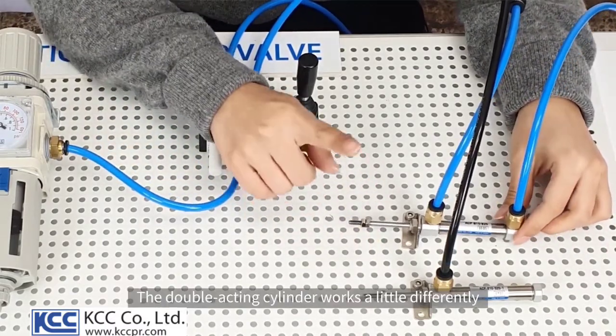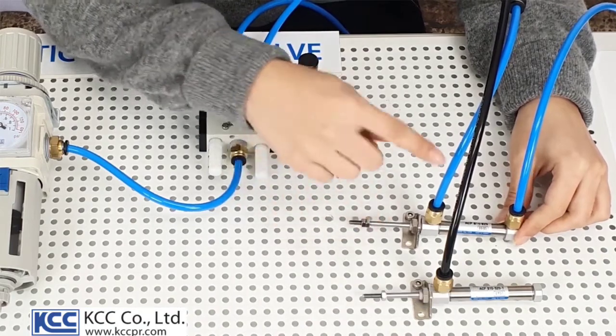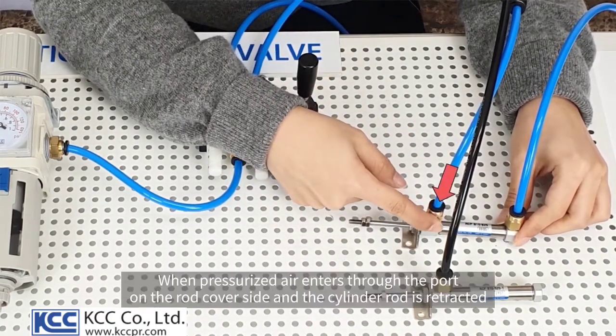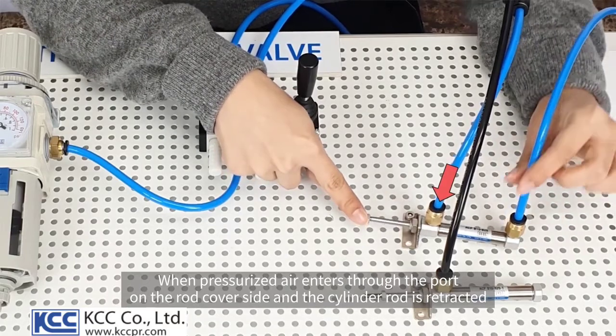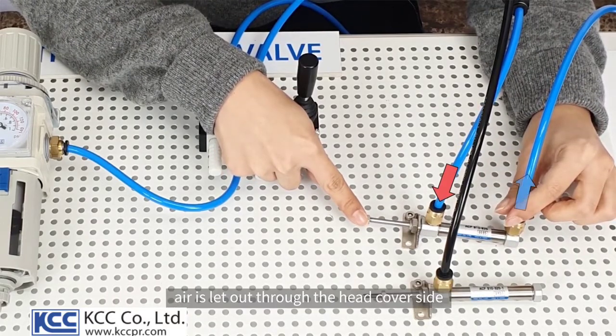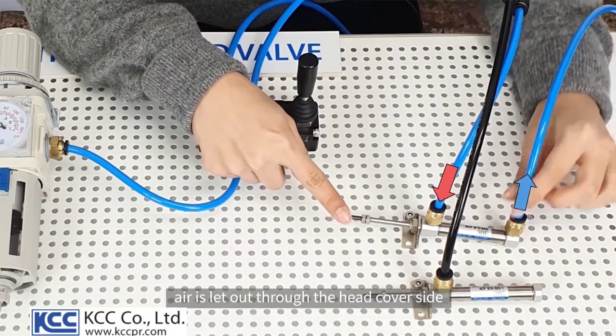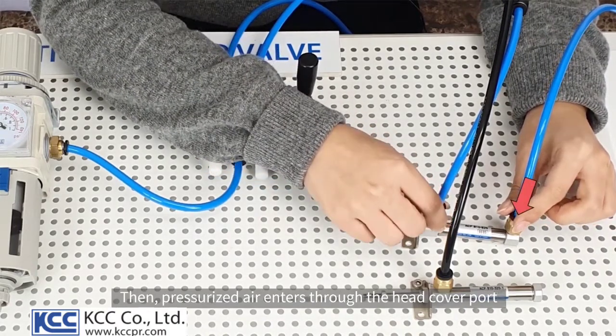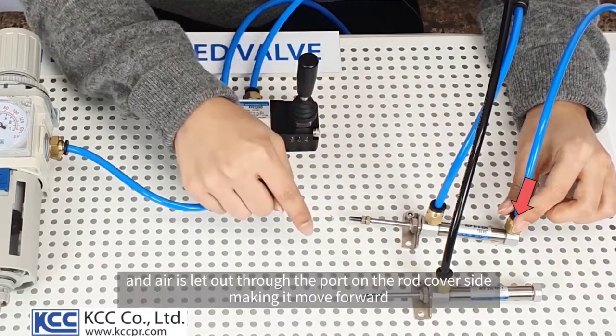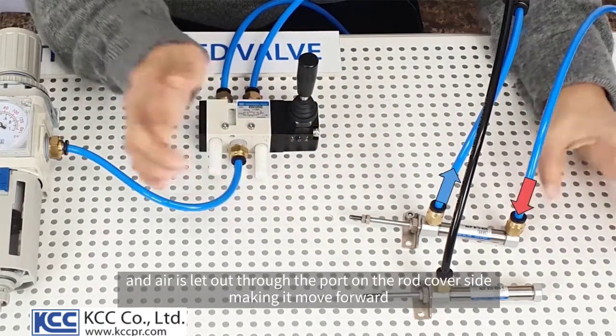The double-acting cylinder works a little differently. When pressurized air enters through the port on the rod cover side, and the cylinder rod is retracted, air is let out through the head cover side. Then pressurized air enters through the head cover port, and air is let out through the port on the rod cover side, making it move forward.